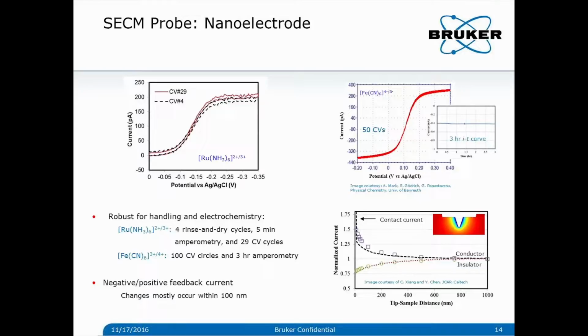Stability: I just showed you several examples in the slide that Ravi showed here. We can do 100 CV cycles. We do 3 hours of amperometric measurement, and you can see that the tip is really stable. We have customers that use the same tip for more than a week, daily. So the tip is actually quite robust. For a nano electrode, the well-known issue is not the performance itself, it's the handling. Most of the time, you need to be careful with electrostatic discharge. Of course, I don't want to take too much time. We can talk about it offline. Just send me an email, and then we can continue.